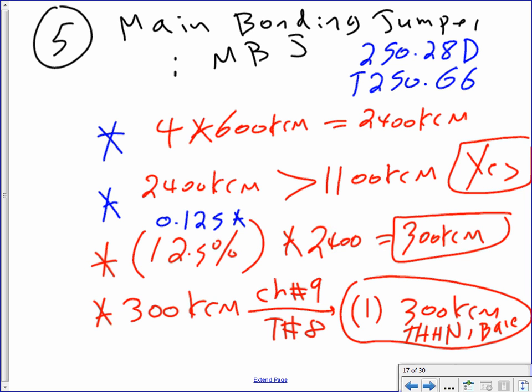So that was just a bare table? It could be covered, bare, or insulated. This is a bonding conductor. A bonding conductor, guys, can be covered, bare, or insulated. Most likely it will be insulated, though. It's not carrying current. Any comments, guys, about the main bonding jumper? The grounding electrode conductor, that's number 6.